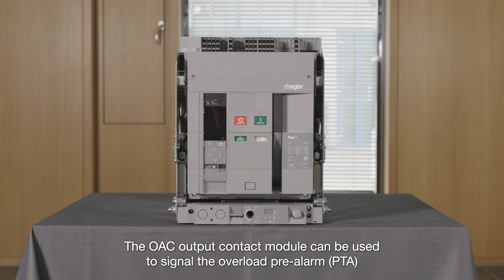The OAC output contact module can be used to signal the overload pre-alarm, PTA, long time delay, LTD, short time delay, STD, instantaneous, INST, and ground fault, GF, protection alarms, and HWF hardware trip system alarms.